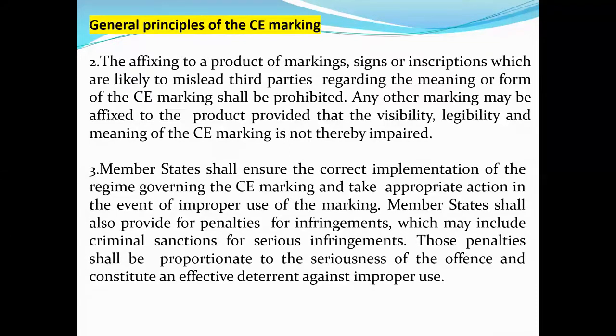I cannot make one single application for the full kit. We have to take the CE mark separately for each, because each acts as a separate device, and we have to pay separate fees for each individual component which makes one medical device, one kit. Similarly, there are many rapid device kits. In a blood testing laboratory, you must have seen a couple of tests, thyroid test, urine test, calcium test, where the samples are withdrawn and separated for different tests. Different biomedical reagents are used. Like that, you have to meet the compliance requirements for each component, each ingredient, and go for the approval, though it is used for one single test.